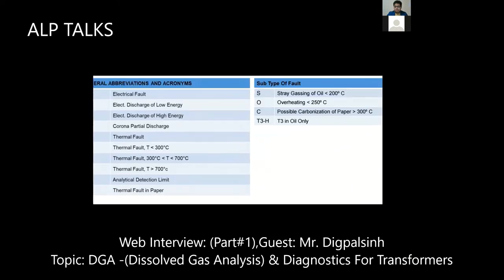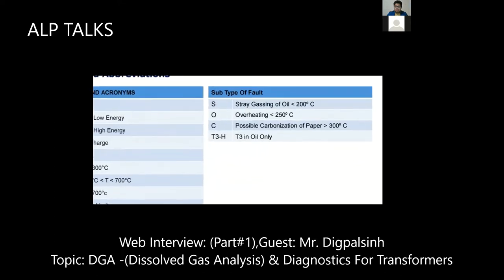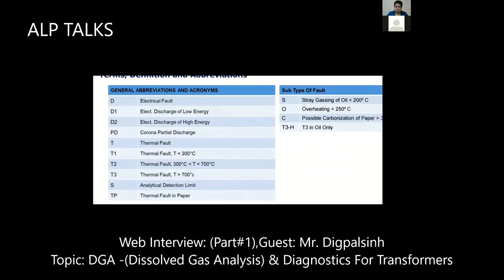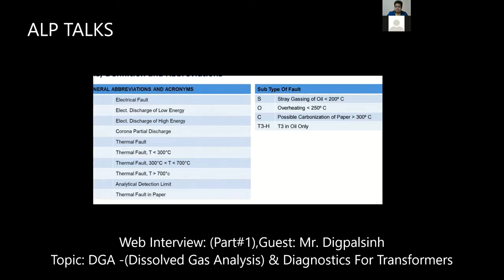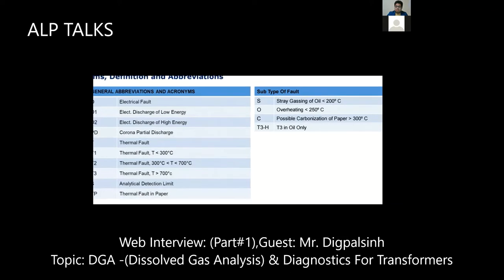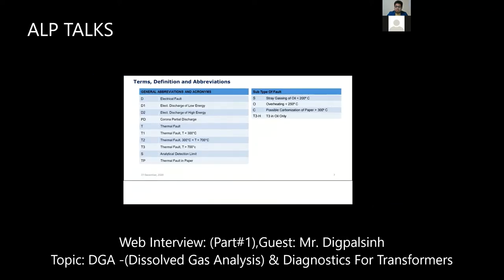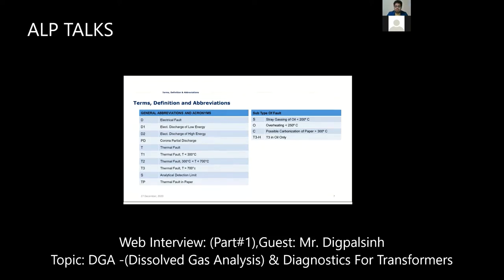And last year CIGRE published one new standard, 771. They have categorized some more faults but not given in detail, only the nomenclature. So S is for stray gassing of oil less than 200, O for overheating, C for possible carbonization of paper, and T3H for thermal fault in oil only. Previously they gave T3 only as thermal fault, and whether it was in paper or oil we had to assume. Now in the figure they have classified T3H only for thermal fault in oil. So these are the main abbreviations, which are always used in DGA.